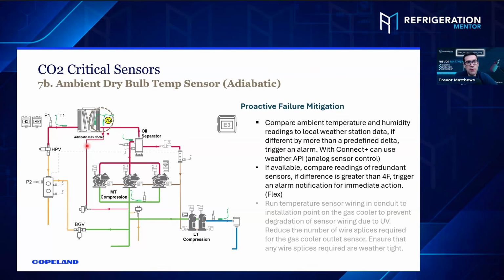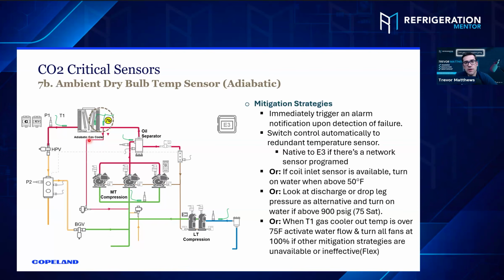Yeah. And it's important to understand what we're trying to do here, once again, which is to keep that system running. Are there any sensors in that system that we can pull data from, to say, okay, we can use this information to keep the system running? That's really what we're talking about. You're right. It's to make anyone listening think about exactly what you said. What else is there that I can point to? I may not have the perfect redundant sensors everywhere, which you won't. So you have to be a little bit more inventive, a little bit more MacGyver. What can I use, knowing refrigeration, that can keep the system running, with pressures or temperatures close to what I had?